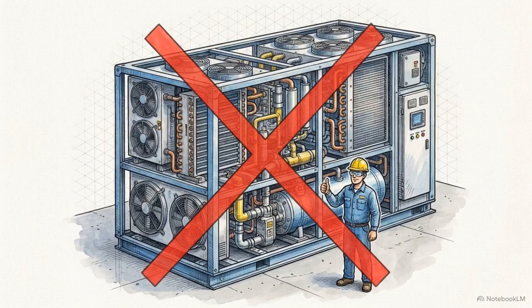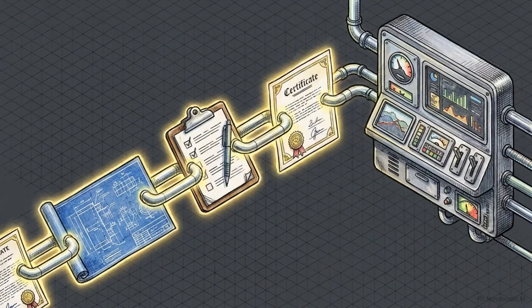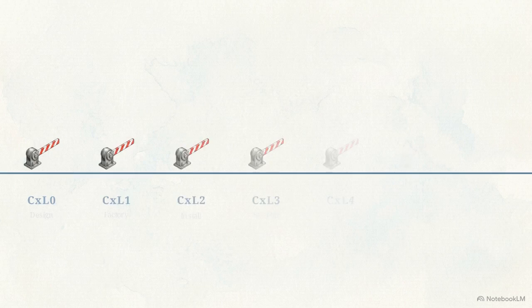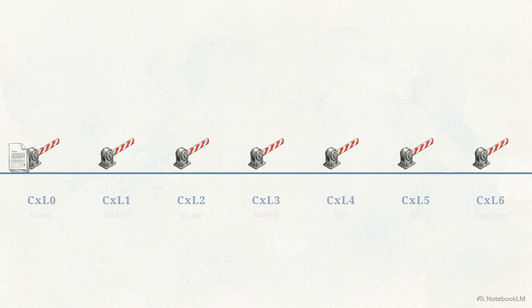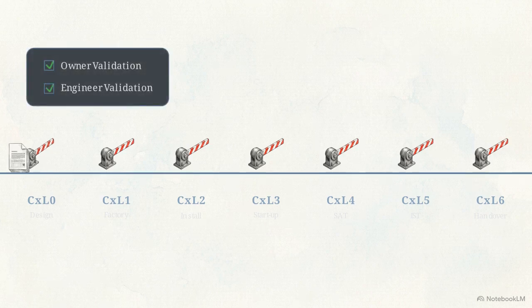Many project teams mistakenly believe a facility is commissioned the moment the equipment is installed and energized. Commissioning algorithmically closes operational risk through a continuous evidence chain that begins at design and ends at handover. The level gates, CxL0 to CxL6, halt progression until validated evidence is provided. An evidence block must slot into the gate to advance.